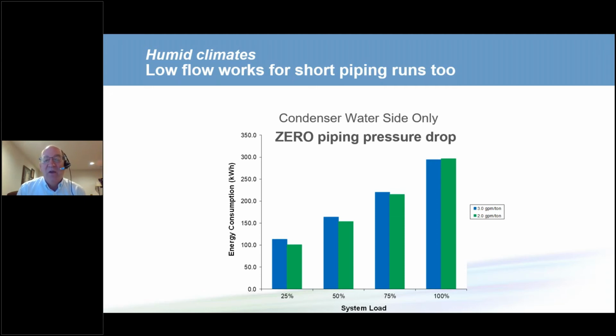Well, what if our pipes magically could give us a 0 pressure drop? Well, in that case, if the pipe gave us 0 pressure drop here at design conditions at 100% load, the system power would be a little bit higher because we will use more power on the chiller than we saved on the pumps and cooling towers. But even though at design conditions the system power is higher, at all off design conditions the system is still more efficient. Therefore, this works even if the cooling tower is on the roof directly above the chilled water plant. We can save energy annually during the year by using lower flow rates and higher delta T's.